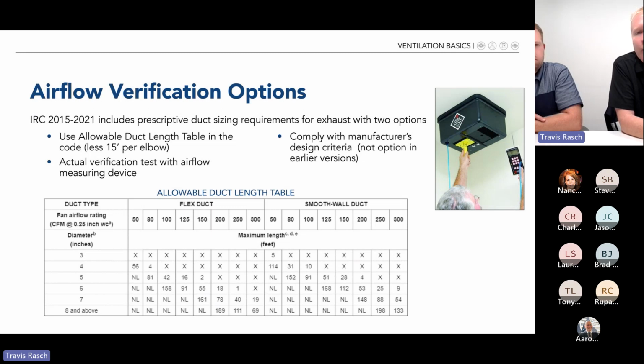So as you look down that, let's look at the column that says flex duct, a 50 CFM fan, 50 being key because that's a requirement in a bathroom. As you can see, for a 3-inch diameter duct, if you look in that cell, there's an X there. That means it's not allowed. You're never going to move 50 CFM in an economy fan with 3-inch ducting. You have to move up to at least 4-inch ducting. So more and more in the building codes, Washington and California have a similar table.